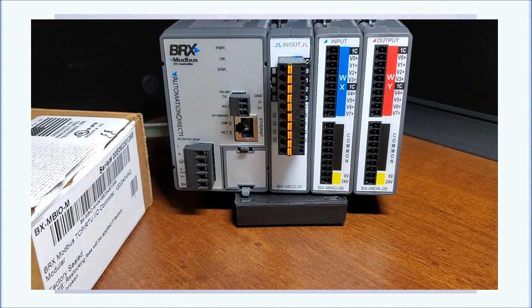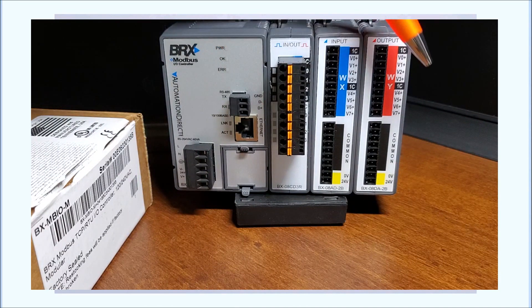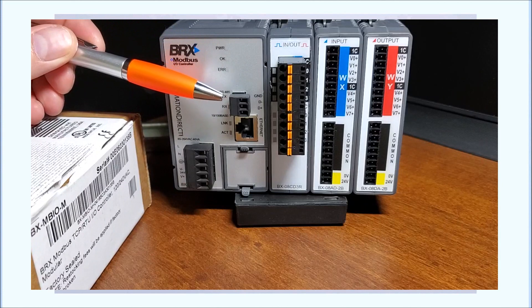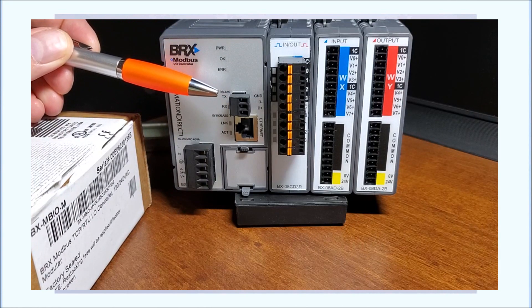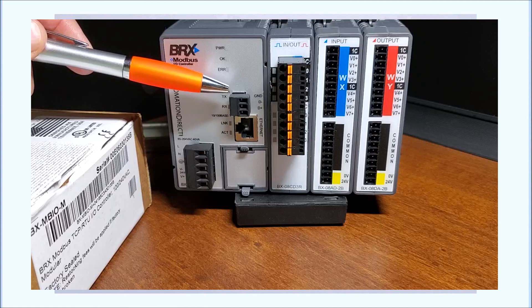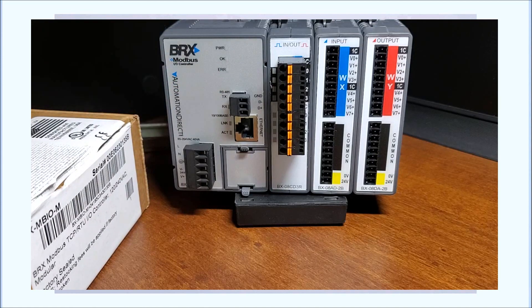We can actually have eight of these different expansion units attached to this Modbus remote I/O unit. Speaking of Modbus, we do have those two connectors. The RTU is our serial connector, which is RS-485, and 485 will transmit at a maximum speed of 115,200 bits per second. We can have up to 31 of these units remotely — so 31 units each with eight cards connected to that unit as a system. Through Modbus TCP, we can have up to 247 of these units connected to a system.